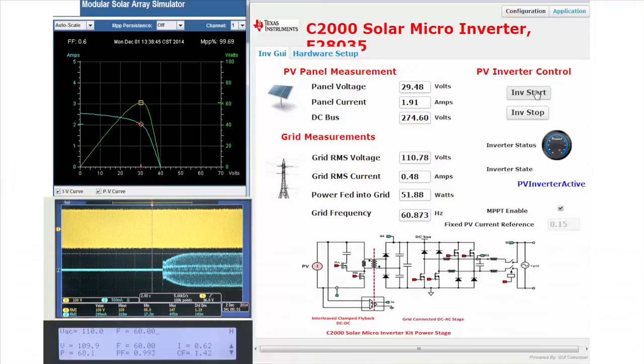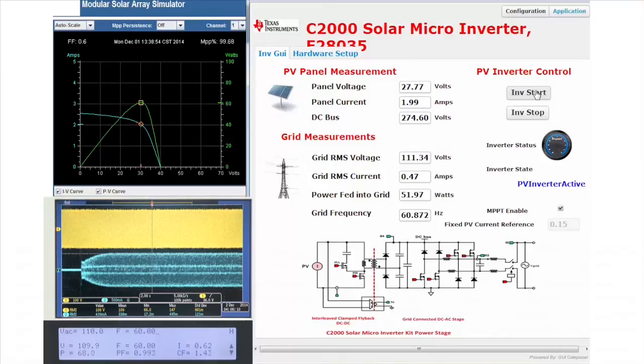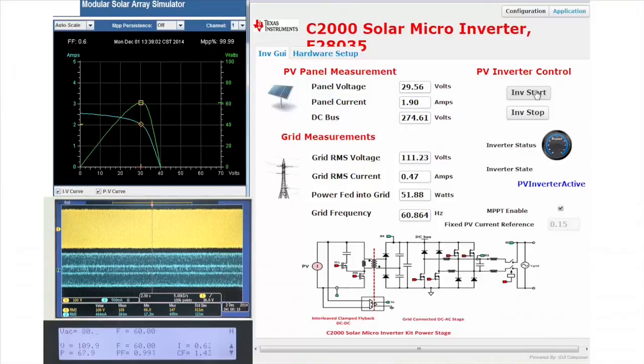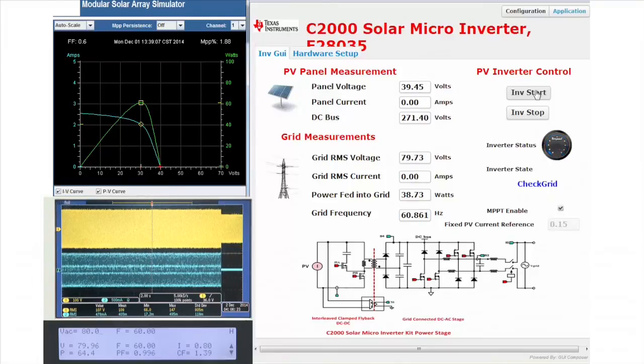Now, it will track back to the maximum power point. To test behavior in case of a grid voltage sag, the AC voltage is changed to 80 volts. The inverter immediately shuts off.